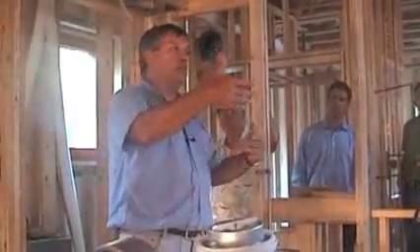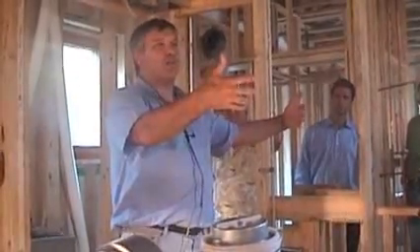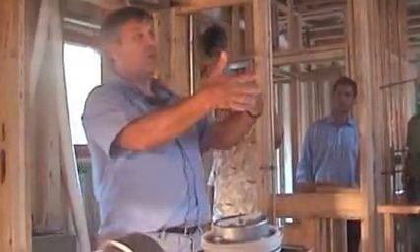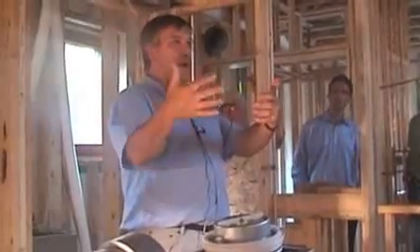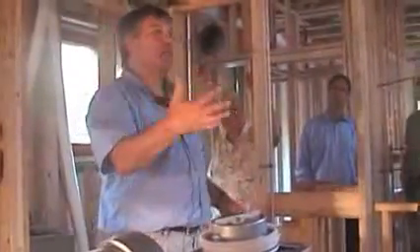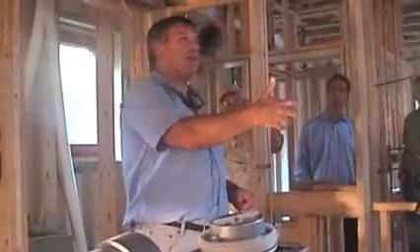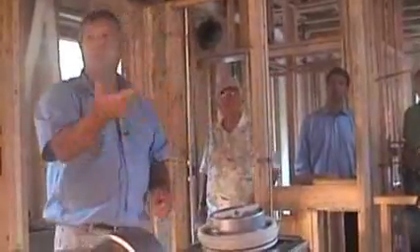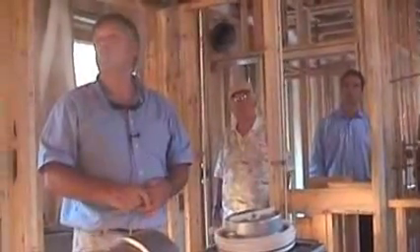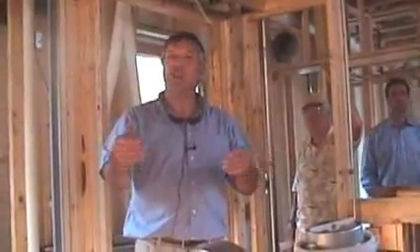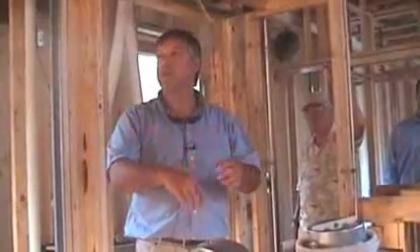So if you've got 90-degree, 90% relative humidity air coming in, and 70-degree, 60% relative humidity coming out of an air-conditioned home, a lot of moisture and heat transfers from that hot, humid air to the outgoing airstream. So now what's coming in is 75-degree air at 70% relative humidity. Enthalpy recovery is about 60 to 65%. I don't have data on that, so we will. We're actually monitoring before and after the coil right now to get some relative humidity data to see what kind of effect it has on the humidity.